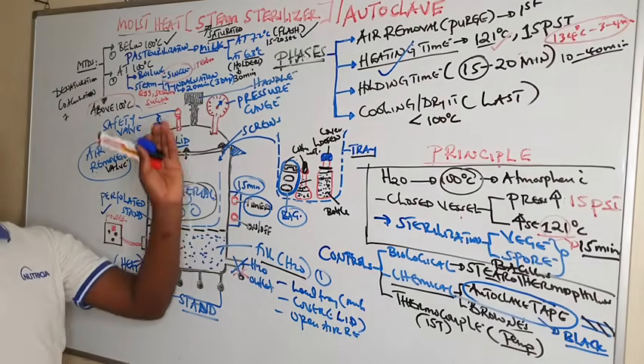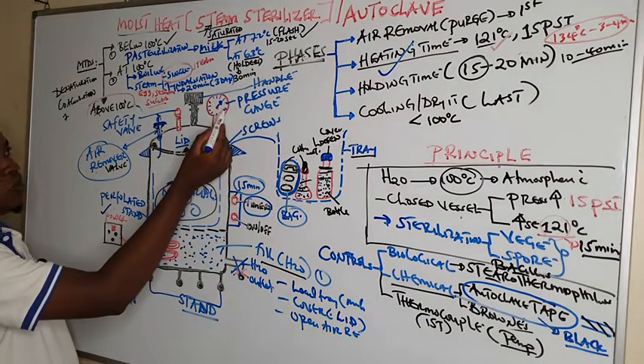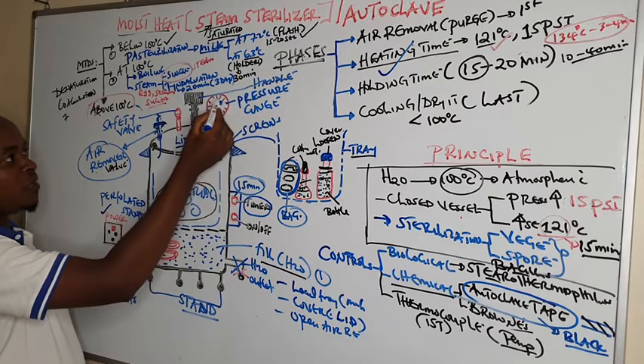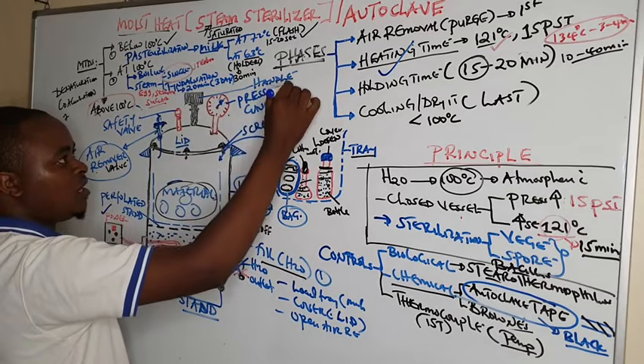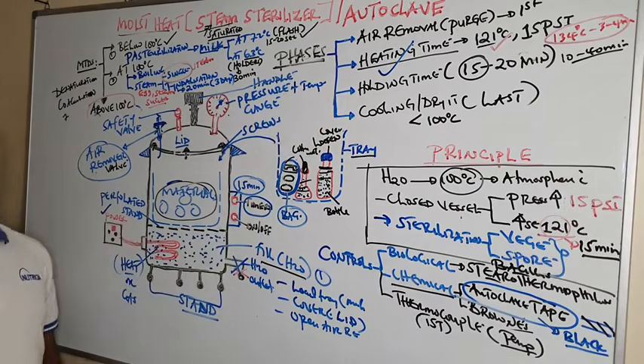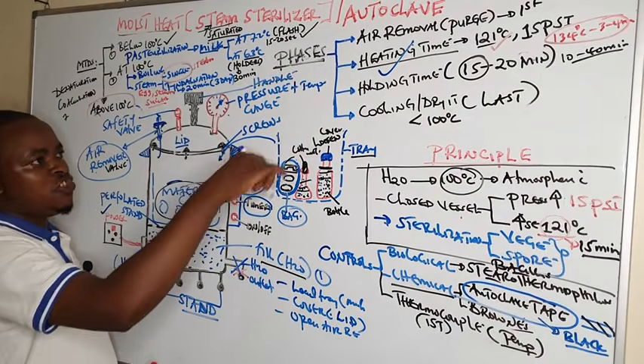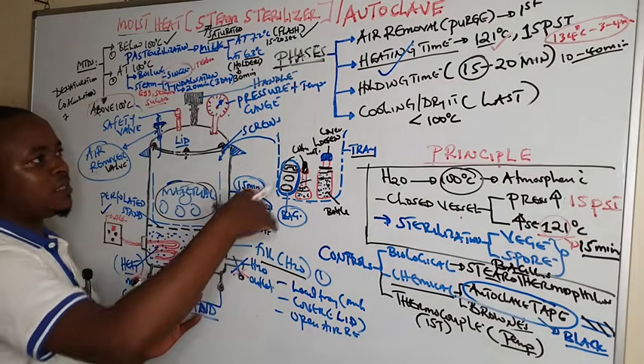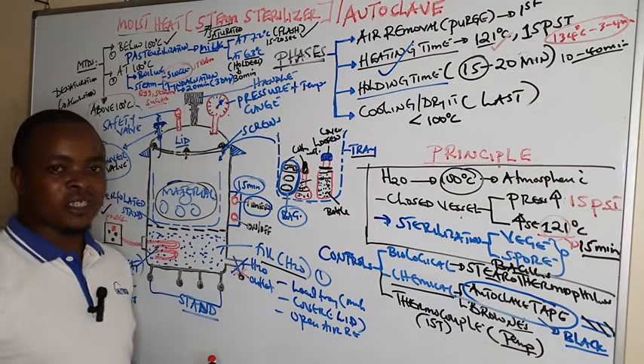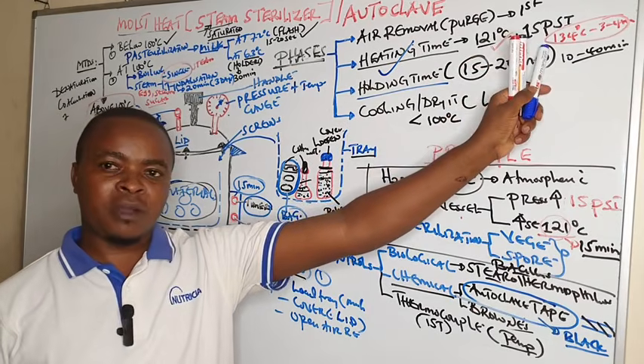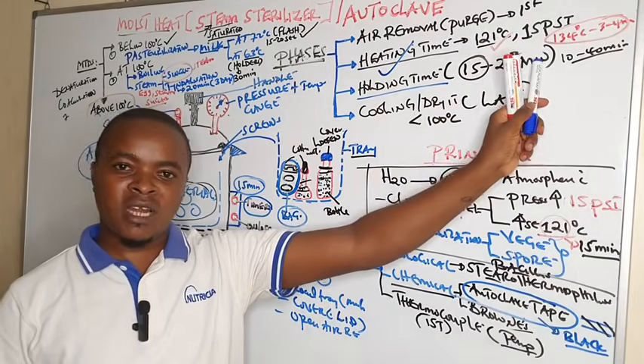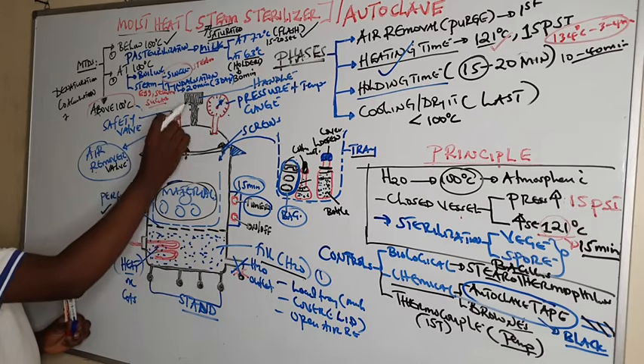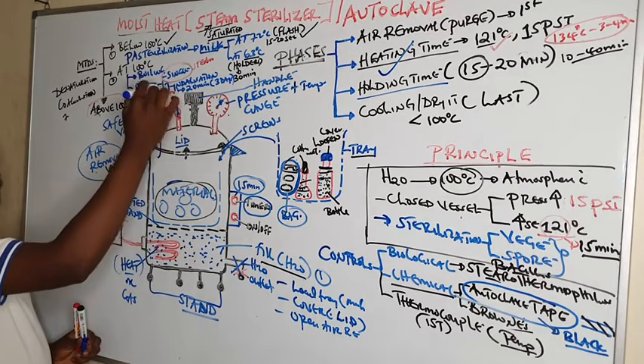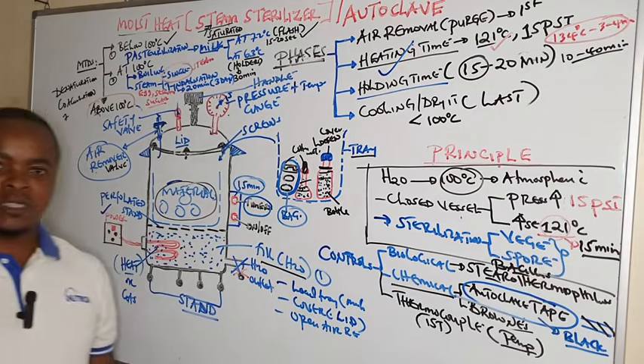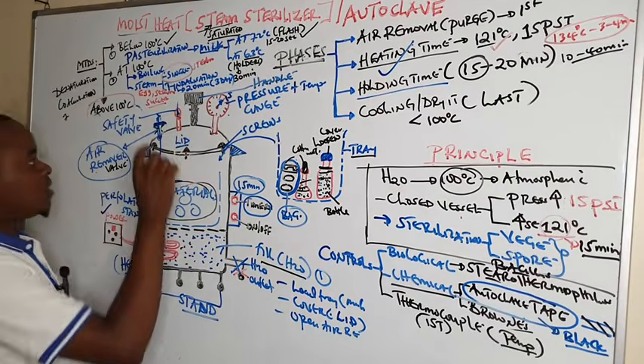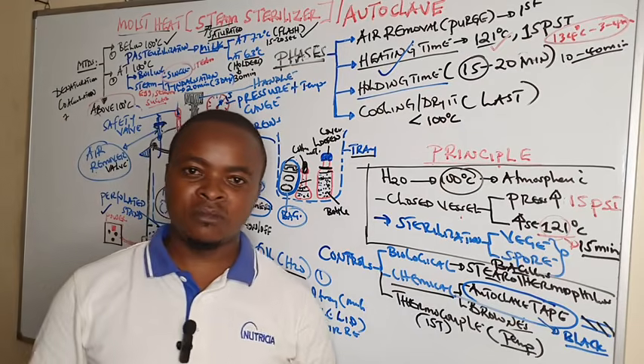That is, temperature will start to rise, and also the pressure, and it is seen on the pressure gauge, whereby the pressure gauge gives both the pressure and the temperature. So it can read the pressure and at the same time the temperature. That is the pressure gauge which we are using. So you can check there. And during sterilization, after switching on, while it is heating and has started sterilizing, during holding time, whenever the pressure goes beyond 15 pounds per square inch at 121 degrees centigrade, there is what we call the safety valve. The safety valve opens and allows steam to escape until it comes back to 15 pounds per square inch at 121. When it comes back, the valve closes and does not allow steam to come out.